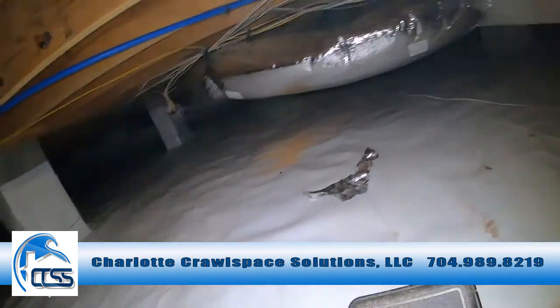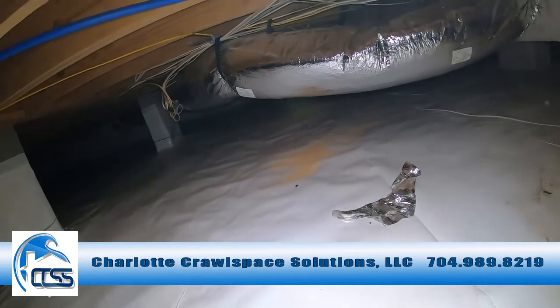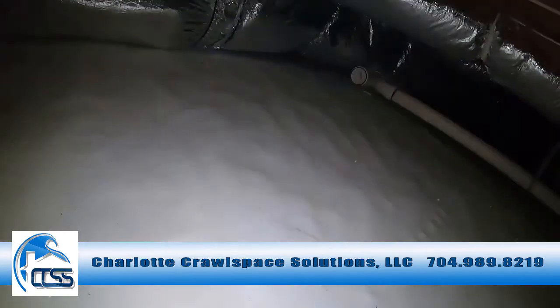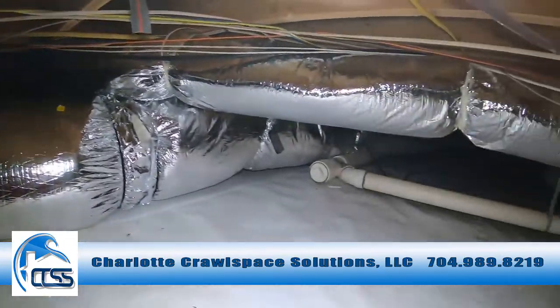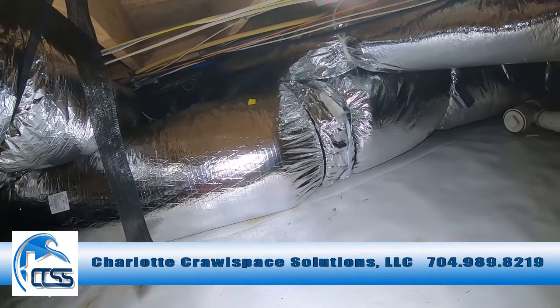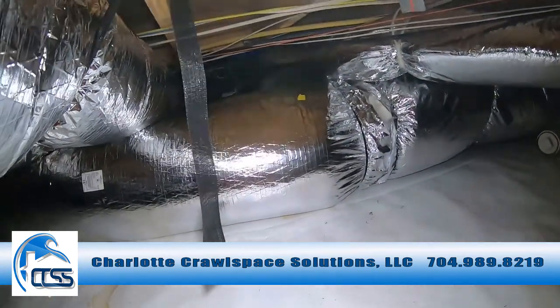You can see here where we have a lot of duct work in the center of this crawl space. It's the first thing I noticed when I did my inspection — how are we going to get air from the left side of this crawl space? Again, it's 4,000 square feet. So how do you get the air to the other side? You've got to use a pipe fan. This main trunk line is running right down the middle of the crawl space, and the other installer did nothing to port the air from this side of the crawl space over to the other side.